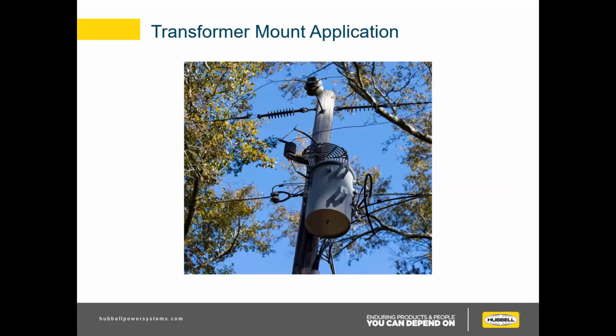So we're going to talk about a transformer mount application for a second. Here's a good example because there's very little lead length here. You have your transformer ground strap, which I think is 12 to 18 inches, so not much. And then we have our little flipper fuse here, and once again, that's super short and direct. We have a nice direct path to the conductor, so it's not putting a mechanical strain on the arrestor, but it's not wasting any length either. This is a very good example of how to get the most protection out of your arrestor.